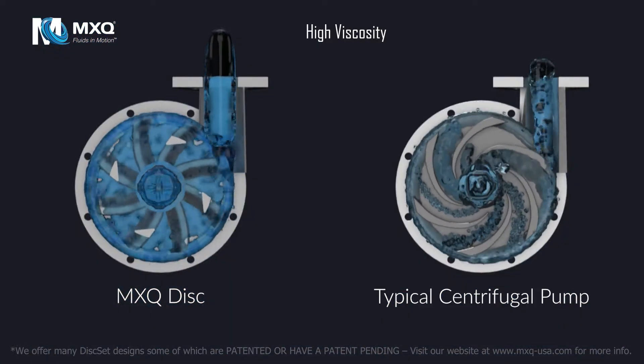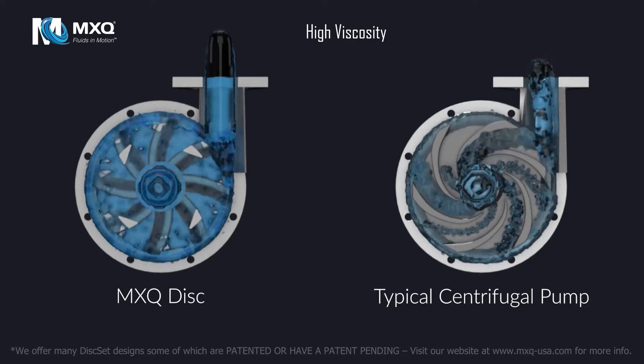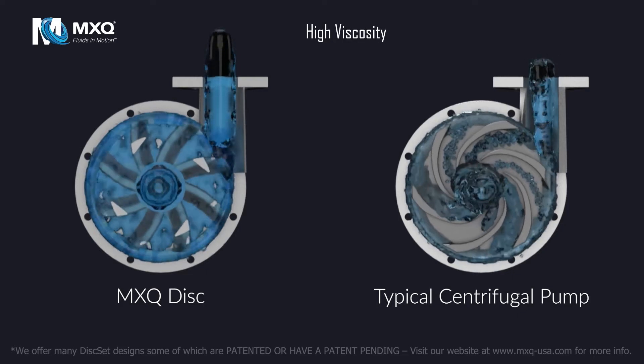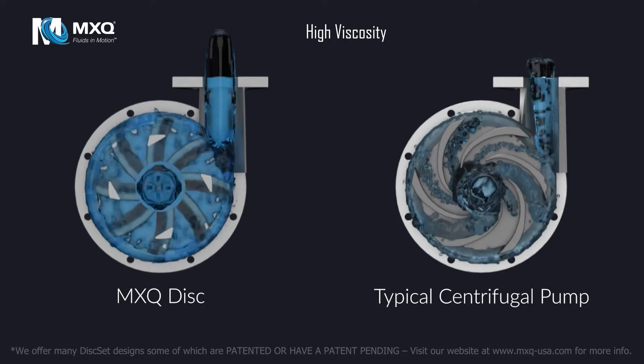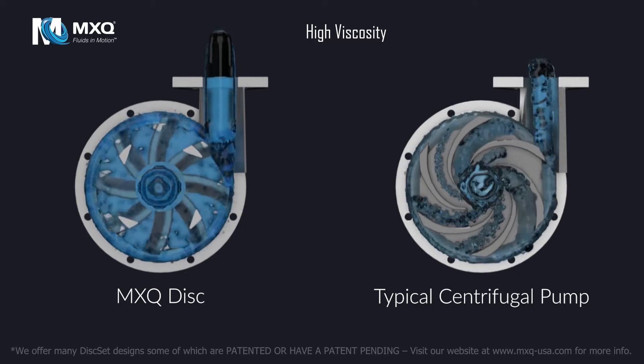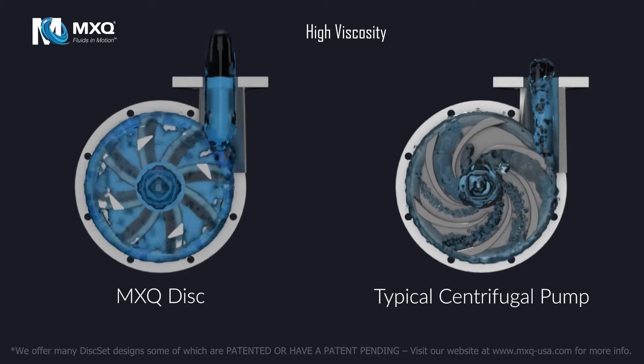High Viscosity. In a typical centrifugal pump, highly viscous fluid is constrained by the impeller vanes. This causes uneven loading because of the fluid's resistance to deformation. The torsional energy generated by the clogging of the vanes eventually results in inefficiency and failure.